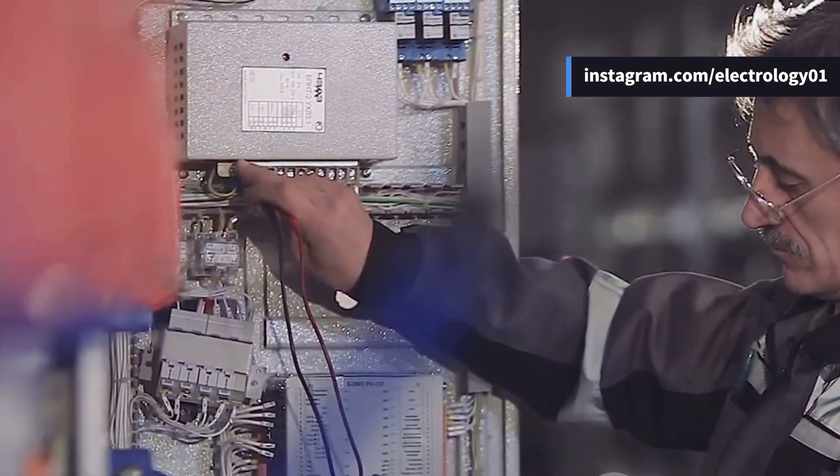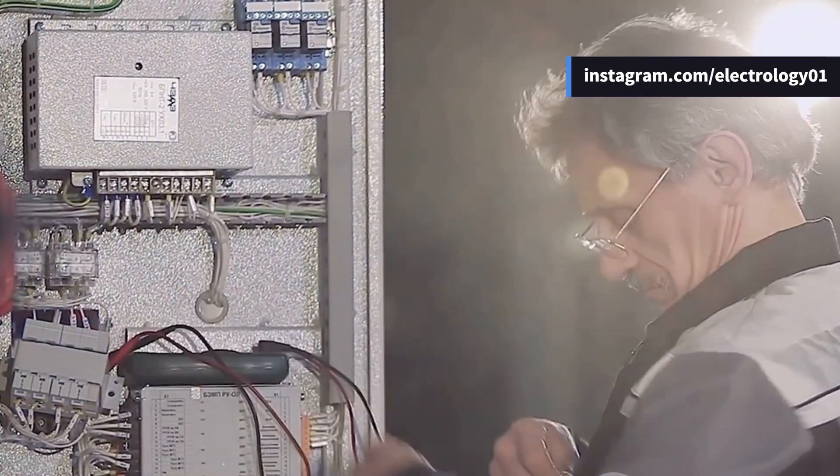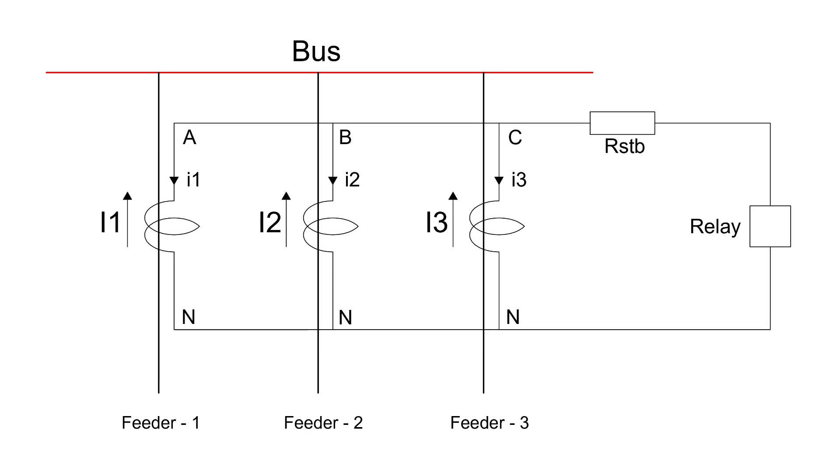Before we dive into the calculation part, let's first understand the purpose of the stabilizing resistor in high impedance differential protection. The stabilizing resistor is used to prevent the operation of the relay in case of a through fault. A through fault is a fault that occurs outside the zone of protection.